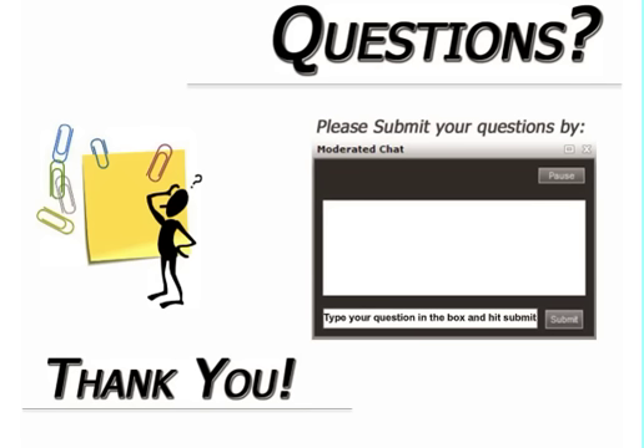All right. We got one from Darren here. Will a deeper depth position produce a noticeable increase in performance? When you get below about 8 feet, there doesn't tend to be much difference, again, depending upon your location. If you have a location like Texas, where they have a terrific cooling load and very long days of high temperatures, that pond loop is going to not only start to rise in temperature, but also obviously the earth around it for a few feet. In those applications, a little bit deeper, you're going to get better thermal performance.